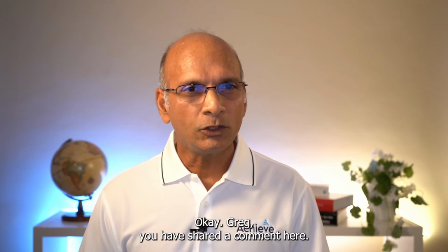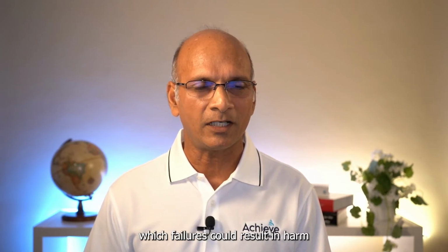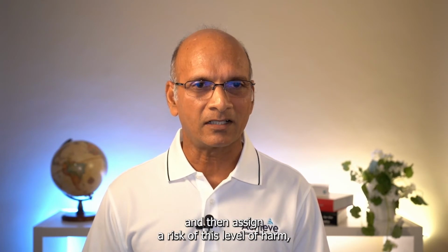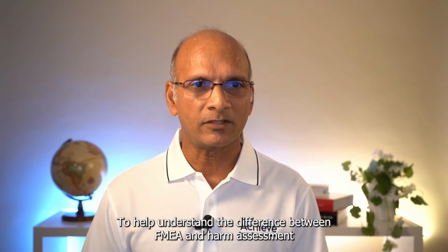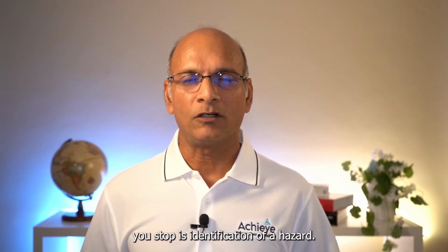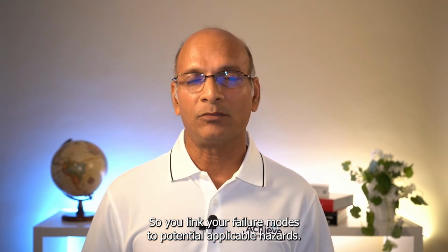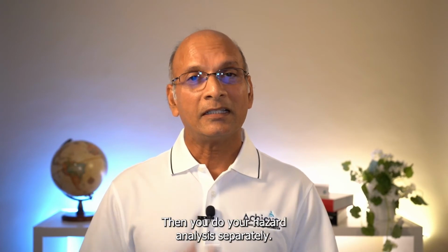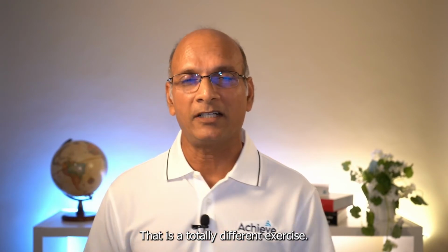Okay, Greg, you have shared a comment here. If using FMEA for harms assessment, how do you determine and identify which failures could result in harm and then assign a risk level of harm, which is different than risk level of failure, to help understand the difference between FMEA and harm assessment? In an FMEA, where I would recommend you stop is identification of a hazard. So you link your failure modes to potential applicable hazards. That is where you stop. Then you do your hazard analysis separately, where you link the hazards with hazardous situations and harms. That is a totally different exercise.